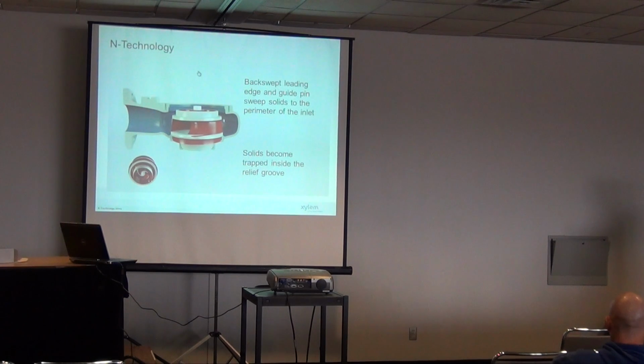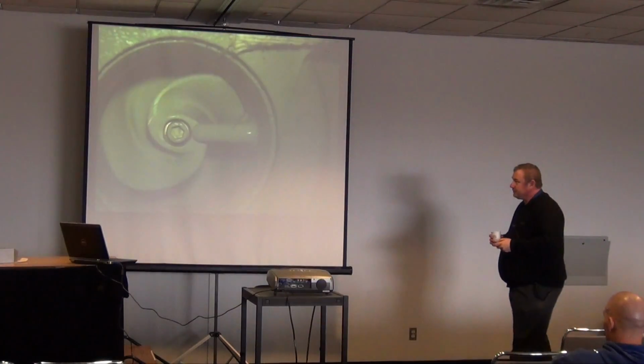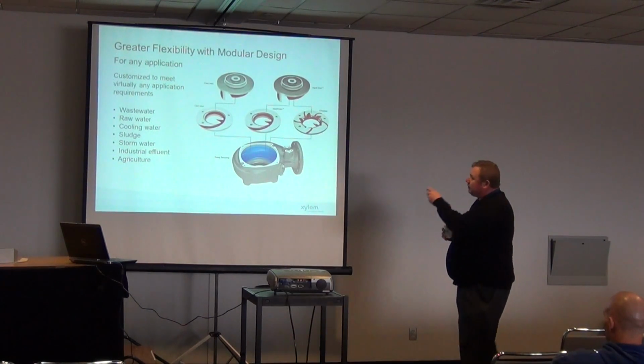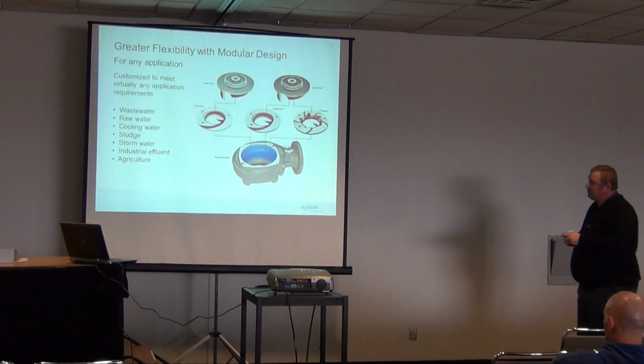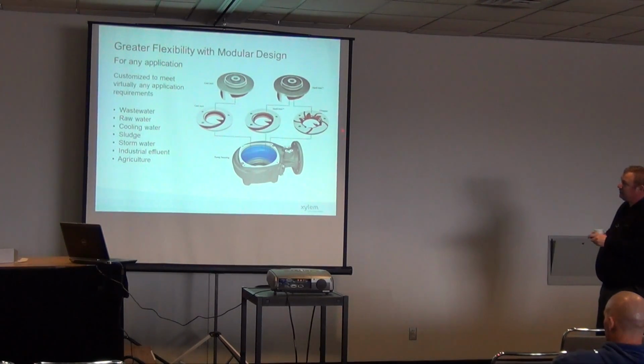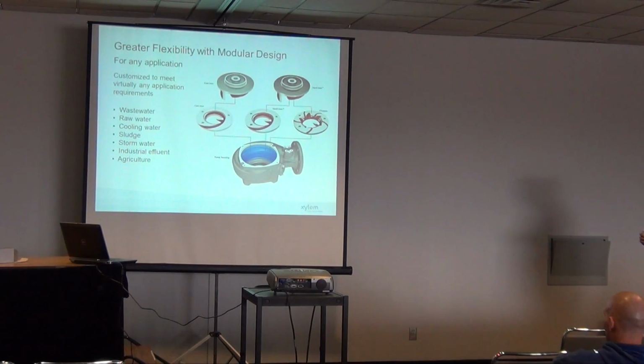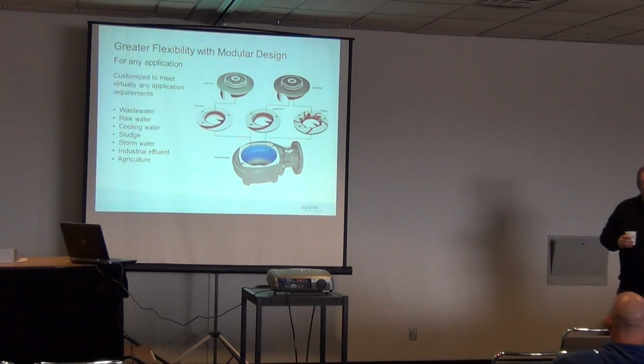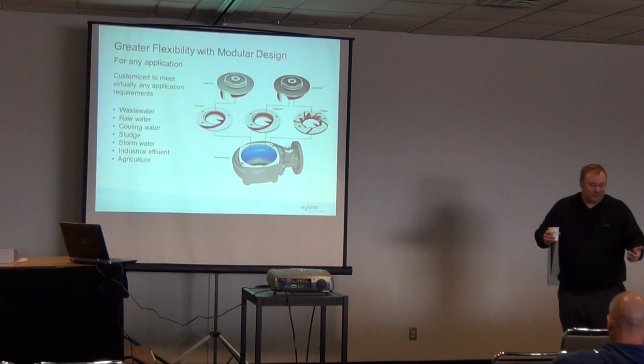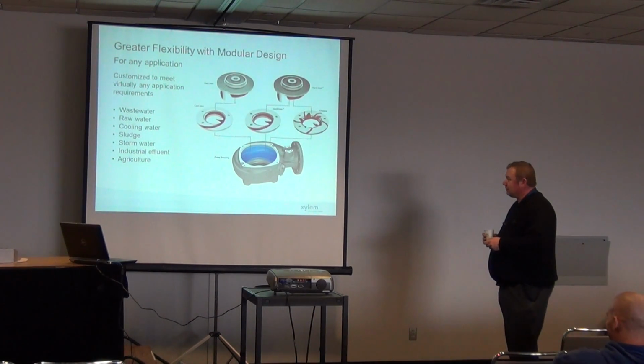And once a soft clog phenomenon gets bigger, you can actually clog the pump entirely, and that means labor calls. That means going out to the site, pulling the pump, extracting the material out of the pump, and then moving on. Modular system where we can do the standard end, and then we can put a different insert ring inside that volute as well to get a chopper pump as well. So it's a modular system. So for this kind of application, institutions, prisons, nursing homes, things of that nature where we tend to have some odd things that might get into the stream that we normally don't see in standard domestic wastewater.